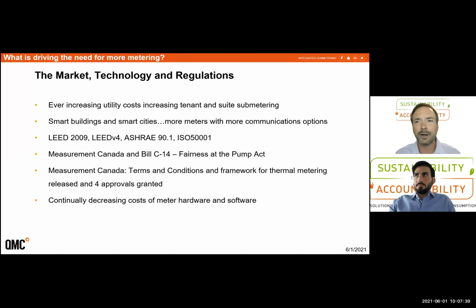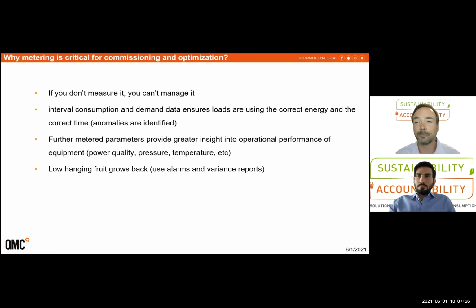And why is metering critical to commissioning and building optimization? Well, our old adage, if you don't measure, you can't manage it. If you don't see where your utilities are being utilized and when, then it's very hard to manage them. And we use interval data, consumption and demand data to ensure that loads are being utilized properly. And obviously we're identifying anomalies and setting alarms along those systems. And there's even more parameters available in more advanced metering, so you can better judge how systems are working. So we're talking about power quality, pressures, temperatures. All this data is available from good meters and good meter systems.